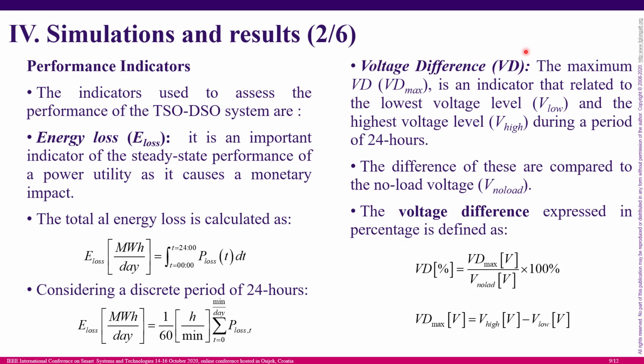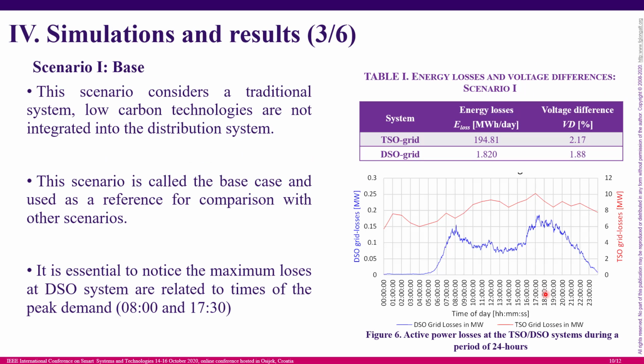And then we have the voltage difference indicator, and this indicator is related to the lowest voltage level and the highest voltage level during the 24-hour period. And here you can see the equations used for the calculation, okay? Then we have a few scenarios. Scenario one is the base case, and it is considering just the loads, and it's not considering any kind of low carbon technology. Okay, this is used as reference for comparing all the other scenarios. The idea is to see the benefits or negative aspects of including the low carbon technologies.